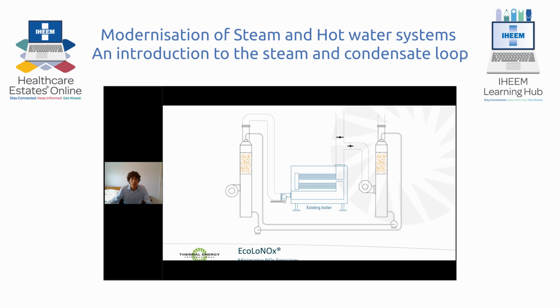As you've seen earlier on in the presentation, we have a flue on this side of the EcoLoNOx system, and by adding additional heat sinks, we can further increase the heat recoverable. Another advantage for heat recovery of humidifying the combustion air is you increase the dew point, or the temperature that we can recover in the flue section. This system is suitable for retrofit or new build applications.